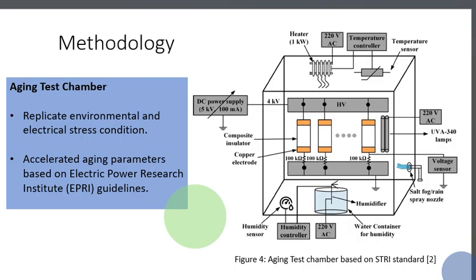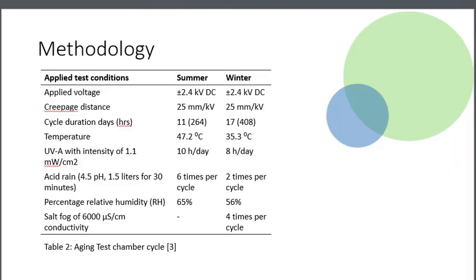To simulate real surface conditions, most of the studies reviewed utilized accelerated aging tests. The aging tests were conducted using chambers designed based on STRI standards. These chambers replicate environmental stresses such as pollution, moisture, electrical stresses, and temperature variations. The accelerated aging parameters are commonly guided by Electrical Power Research Institute (EPRI) standards to replicate long-term outdoor exposure within a short time frame.